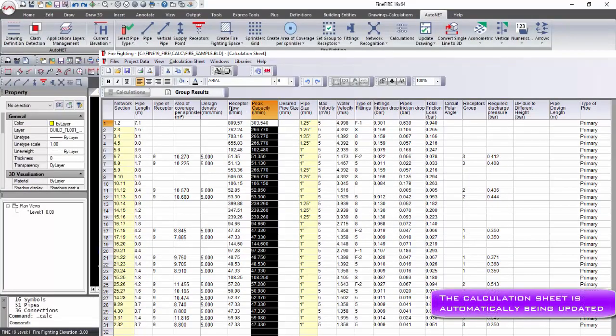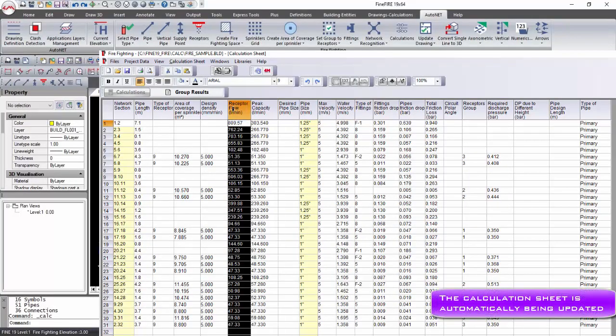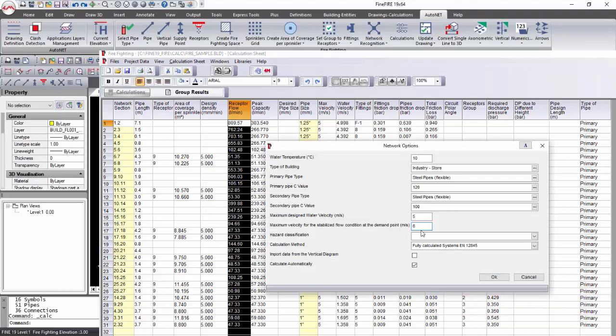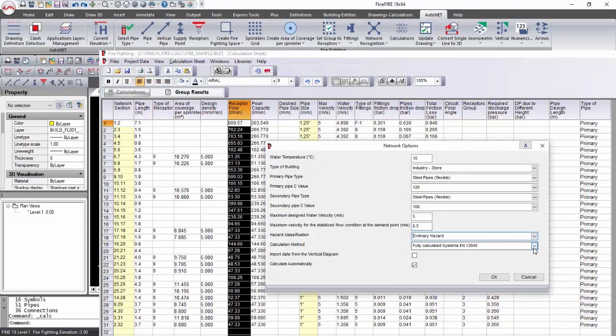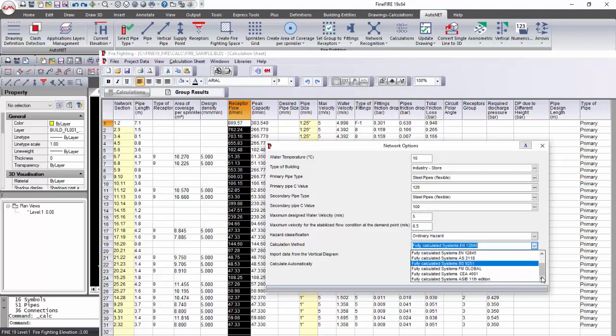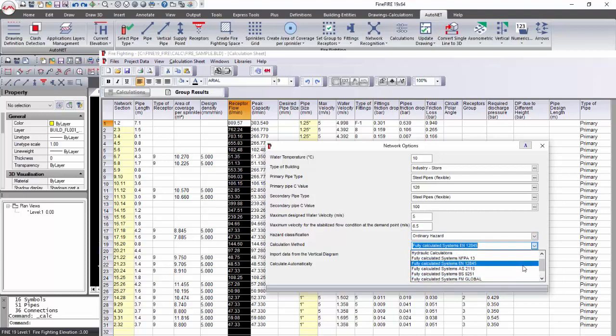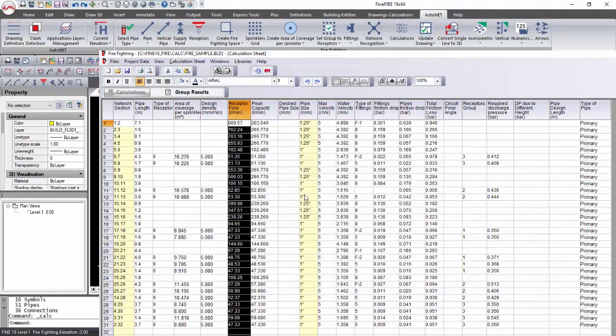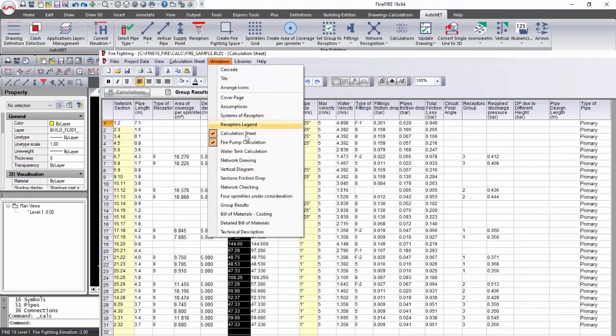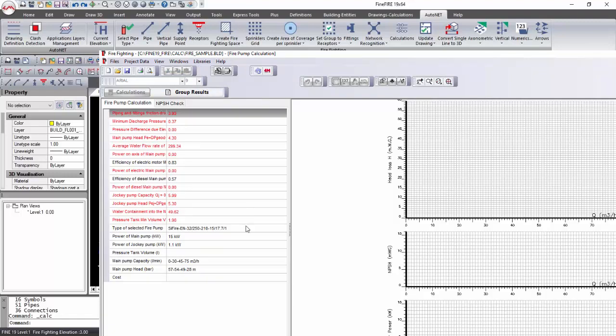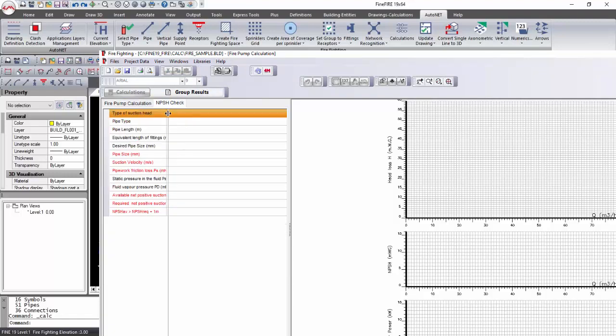You can view the calculations in the Windows Calculations sheet. This sheet is the core of the firefighting system calculations. Fill in the network's project data with the general specifications of your project such as type of pipes, maximum velocity, and calculation method. In the Windows Fire Pump Calculation, you can select the fire pump, calculate the motor power, and run an NPSH (Net Positive Suction Head) check.